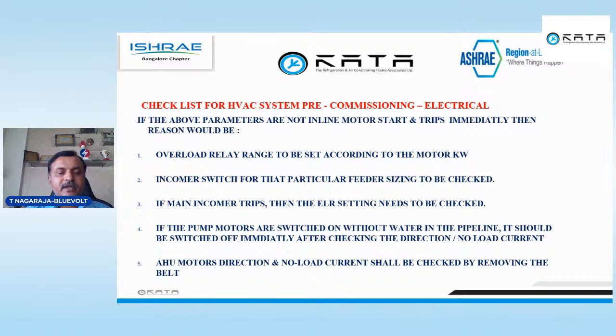What will happen? A new panel will come. There is no problem here. What is the new panel? You switch on, then it will trip. Immediately they call, your panel is tripping. But they will not set the overload relay at the factory, because for our motor, whatever is on the nameplate, we have to set accordingly.